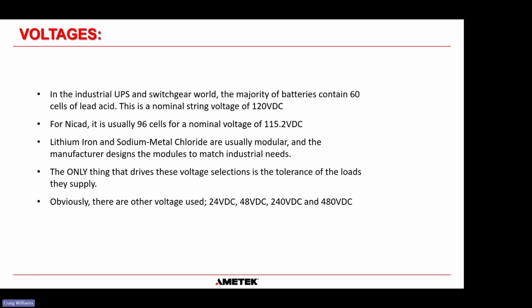For lithium ion and sodium metal chloride, which are usually modular, the manufacturer designs these modules to match those industrial needs. Basically, the lithium ion and sodium metal chloride or salt battery manufacturers know that we're going to use those batteries in an industrial environment. So they match their modules to match this lead acid 120 volts and NiCad 115 volts, to make sure it's roughly in that ballpark. The only thing that drives these voltage selections is the tolerance of the loads that they supply, which we'll go into in just a moment.